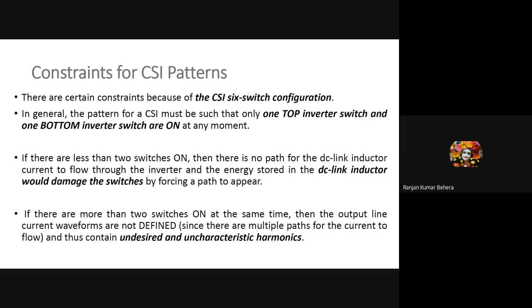Another thing is that when the waveforms have undesirable characteristics, for example, upper 1 switch on, lower 2 switches on, then when 2 switches and upper 1 switch, that will create another uncharacteristic harmonic. Harmonic is normally an integer, but we will get harmonics in terms of 2.5th harmonic, like that. That is called the undesirable harmonic.